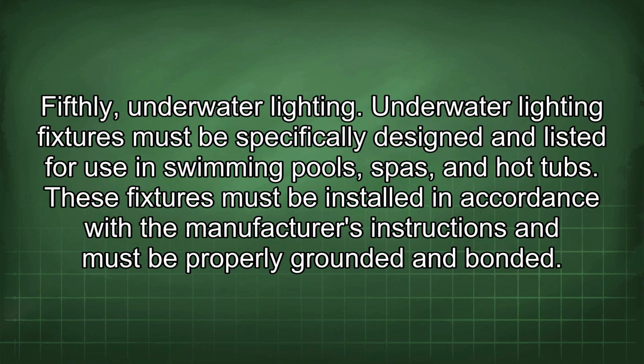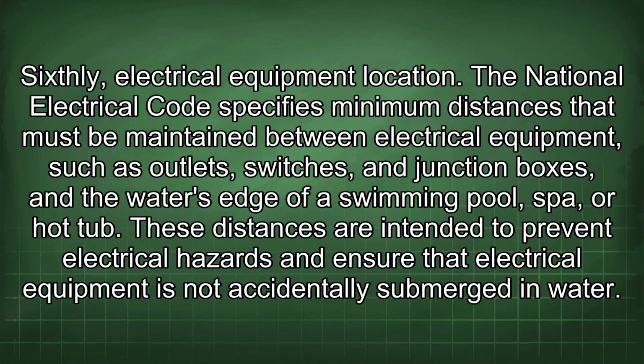Fifthly, underwater lighting. Underwater lighting fixtures must be specifically designed and listed for use in swimming pools, spas, and hot tubs. These fixtures must be installed in accordance with the manufacturer's instructions and must be properly grounded and bonded. Sixthly, electrical equipment location. The National Electrical Code specifies minimum distances that must be maintained between electrical equipment, such as outlets, switches, and junction boxes, and the water's edge of a swimming pool, spa, or hot tub.